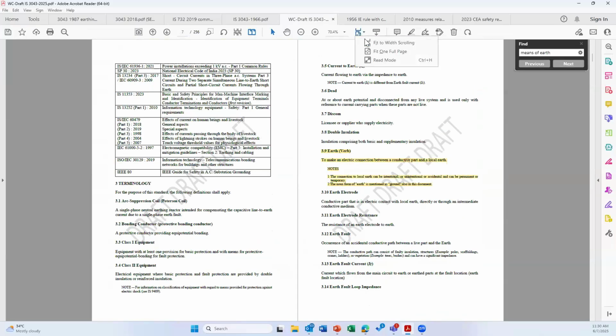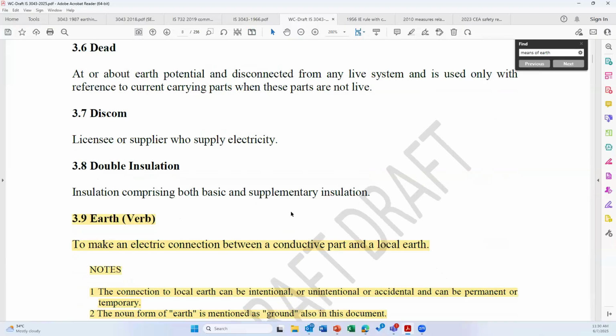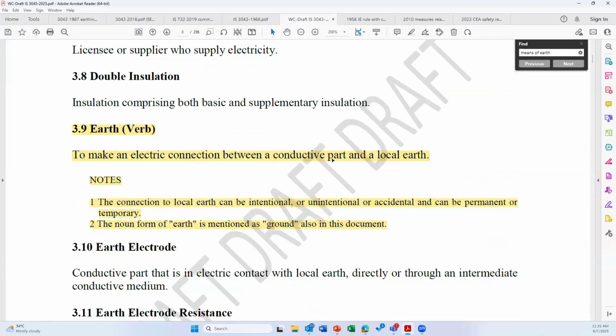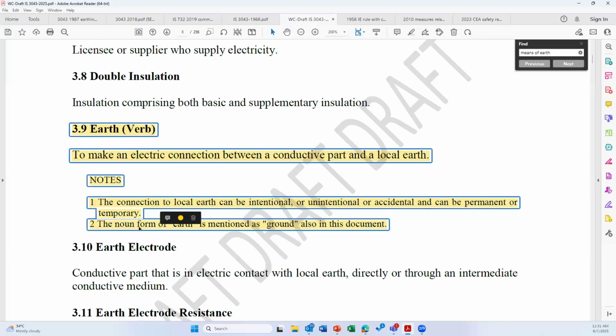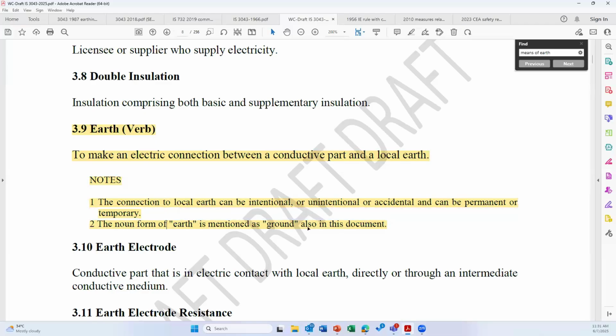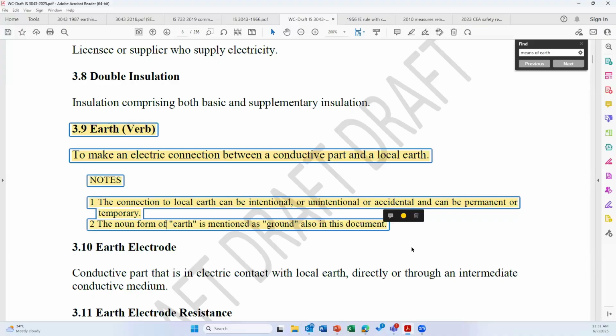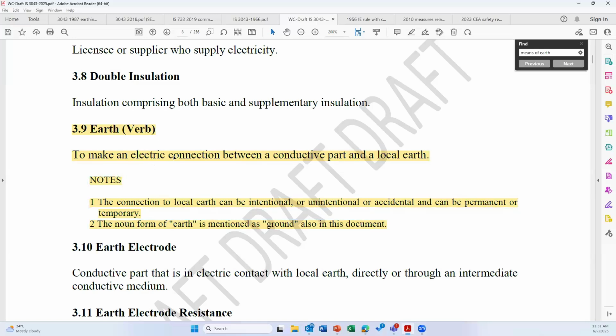Coming to the definition of earth, which is adopted in the IS 3043, you can see here, earth as a verb means an electric connection between a conductive part and local earth. Local earth again has a definition, which is similar to the definition from the IEV, International Electrotechnical Vocabulary. Note that the connection to local earth can be intentional, unintentional, or accidental, and can be permanent or temporary. Now, very interesting, you can see here the noun form of earth is mentioned as ground also in this document. For example, underground cables, UG cables, or underground connections. So, ground is also used somewhere in the standard, but the meaning of ground here is the actual soil, the actual ground, whereas earth means the connection of a conductive part to the local earth. That is how it is.